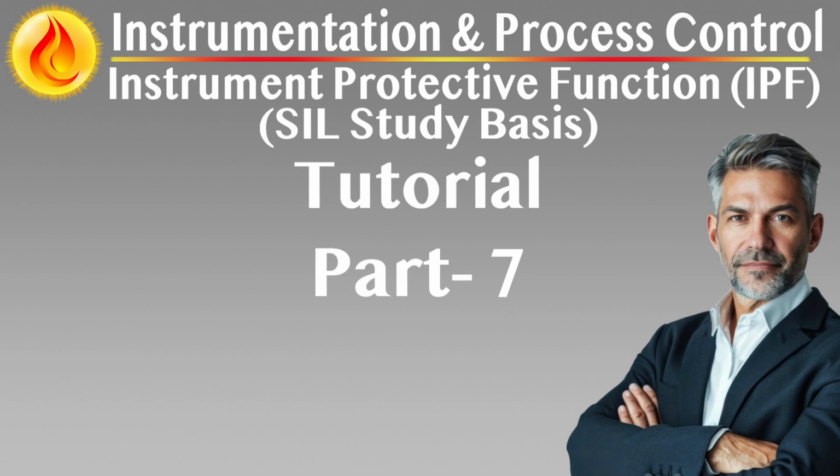Response logic and integration with protective actions. Cause and effect logic. Detectors must be mapped to specific protective actions, such as gas detection leading to ventilation shutdown or flame detection leading to deluge activation. Logic must be deterministic, well-documented, and easily testable.